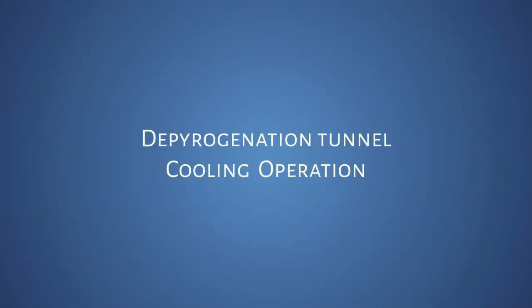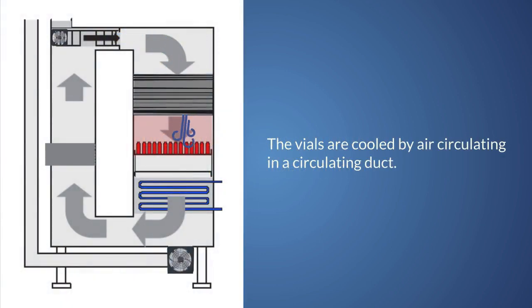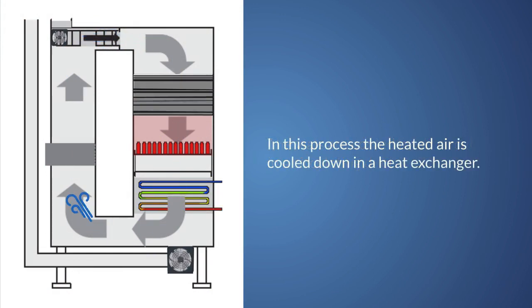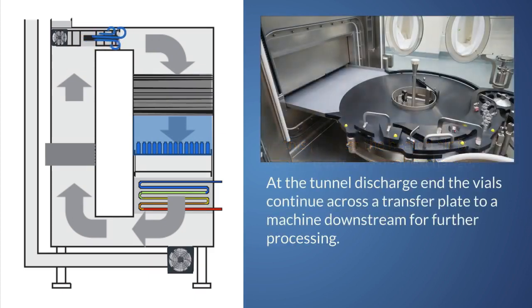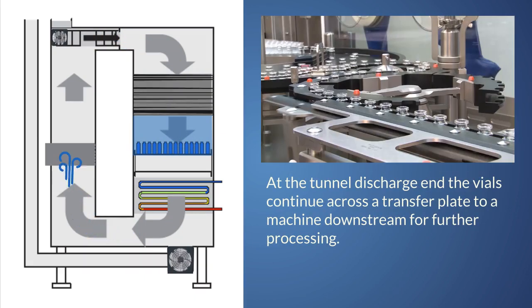Now let's take a closer look at the depyrogenation tunnel cooling operation, where the sterilized and depyrogenized vials are cooled down by flooding them with cold air. The vials are cooled by air circulating in a circulating duct. In this process, the heated air is cooled down in a heat exchanger. At the tunnel discharge end, the vials continue across a transfer plate to a machine downstream for further processing.